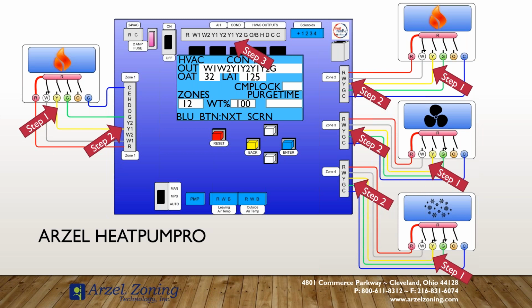So with the Heat Pump Pro, we can view our thermostats individually, and we can focus on that specific thermostat, that specific set of zone connections, because that's our thermostat and our equipment. And we can see where our problem's at on that specific zone. So it might be broken thermostat wire, it might be a bad thermostat. Rather than trying to diagnose all 4 zones in our equipment at the exact same time, we break it down into individual zones. Each zone has a thermostat. Each connection inside the board, zone 1, zone 2, zone 3, zone 4, is our equipment in relationship to that thermostat.